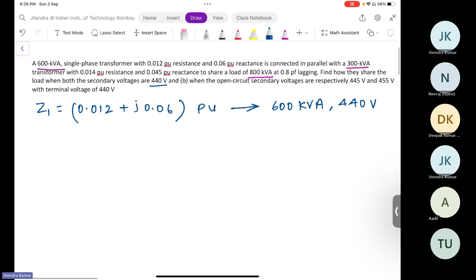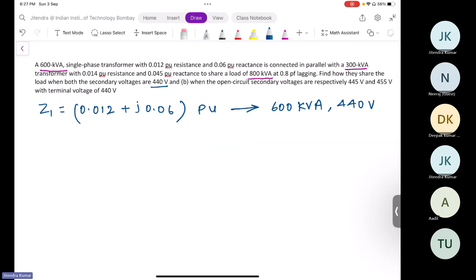Because when we apply the ratio of loading, we have to consider equal amount of base impedance. Z2 will be 0.014 plus j0.045 per unit, with 300 kVA and 440 volts.